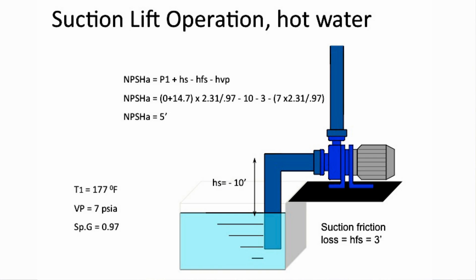Now, if the same pit, same situation occurs, but the water temperature goes up to 177 degrees Fahrenheit, this has a vapor pressure of 7 PSIA, and the NPSH available drops to 5 feet.